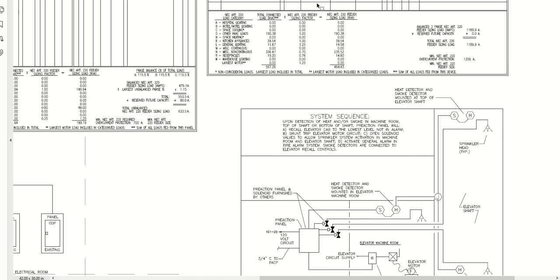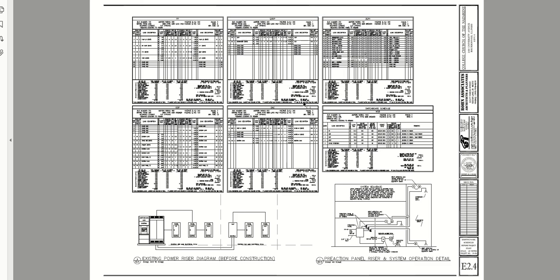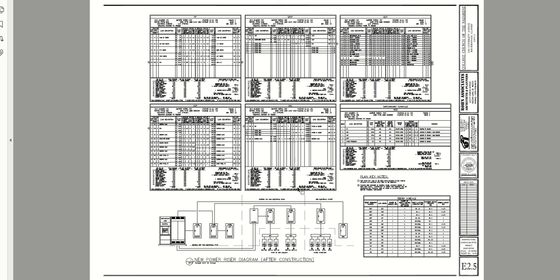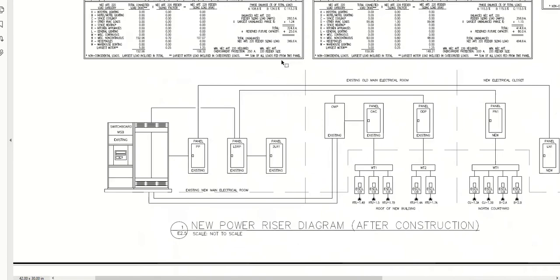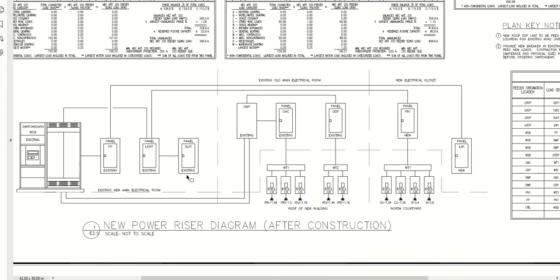Then we go to the next sheet and see the new or revised diagram and the revised panels, so we can demonstrate that we're not overloading panels in this situation. We keep the existing tag on what's existing and show what's new. Here are those wire troughs we talked about for the stuff on the roof and the condensing units in the courtyard. Here we call out enclosed circuit breakers to satisfy the tap rule for each of those taps.